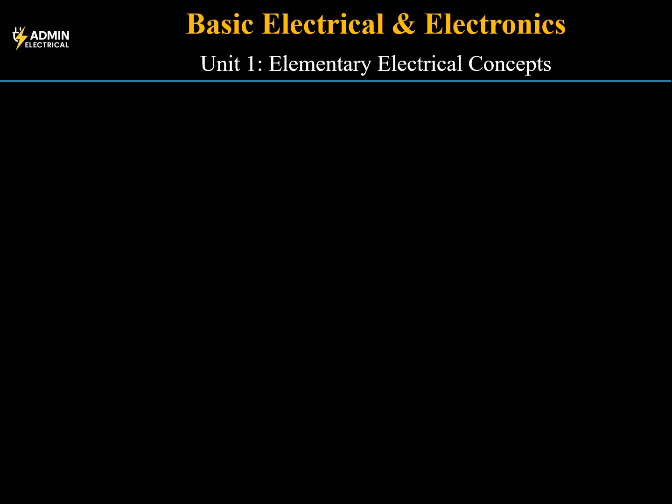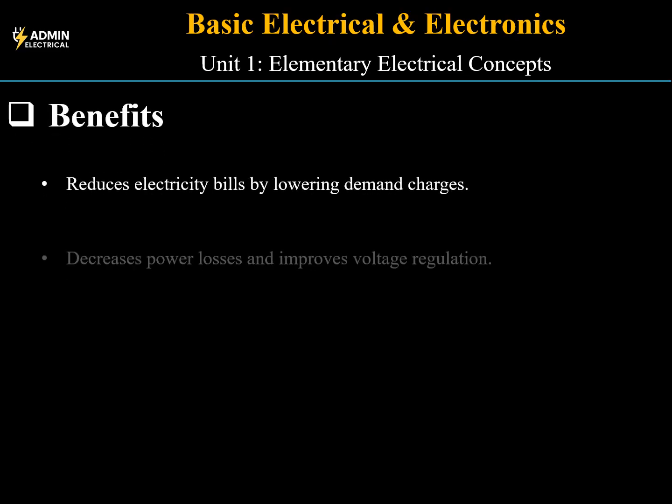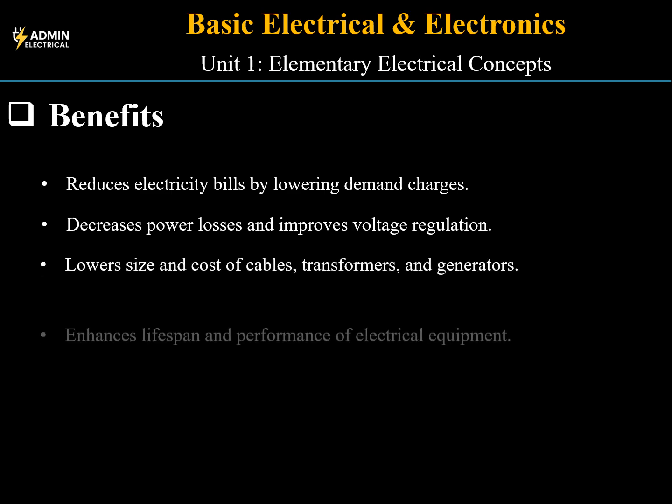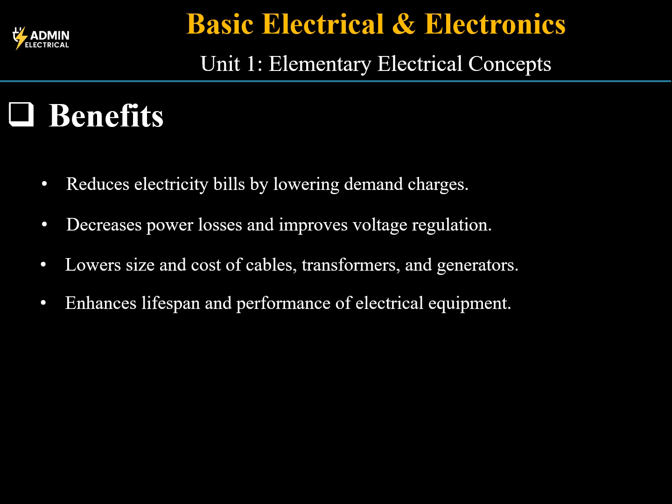Maintaining a high power factor has many benefits. It reduces electricity bills by lowering demand charges, decreases power losses in cables and transformers, improves voltage regulation, allows use of smaller-sized transformers, generators, and cables, and increases lifespan and performance of electrical equipment. It's one of the most effective ways to ensure energy efficiency.